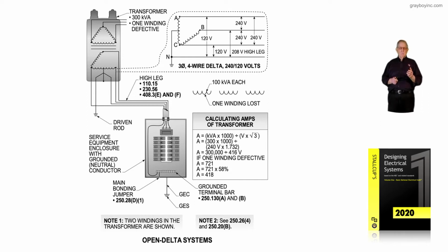So once again, as designers or installers, if we take 120 volts plus 240 and divide that by the square root of 3, that's where that 208 volt high leg you see coming in. I don't mean to be too simple here, but remember the square root of 3 is always 1.732. And that's important in other things that we're going to do in this presentation. So we are reviewing in this figure 4-6 open delta systems.